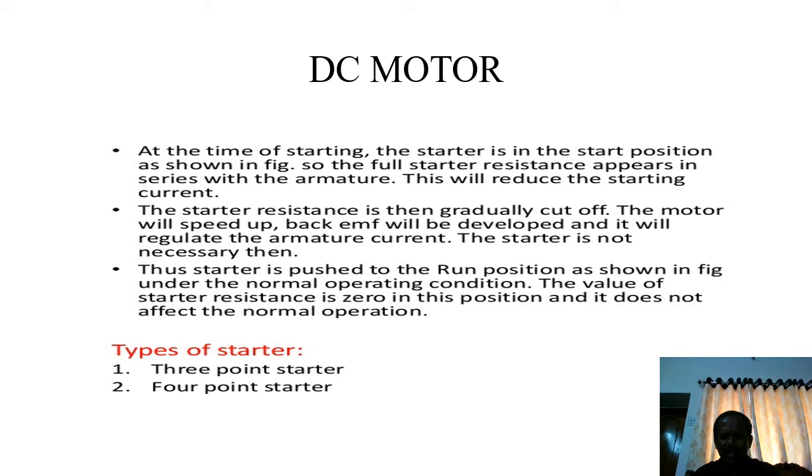Then the starter is not necessary, so the starter is pushed to the run position, shown in the figure. Under the normal operating condition, the value of starter resistance is 0 in this position and it does not affect the normal operation, and the motor will rotate at the actual required speed. So we are using this type of starter, the 3-point starter and 4-point starter.